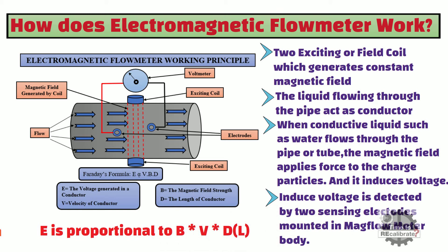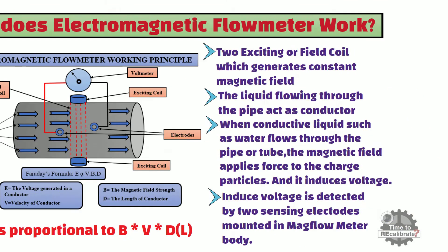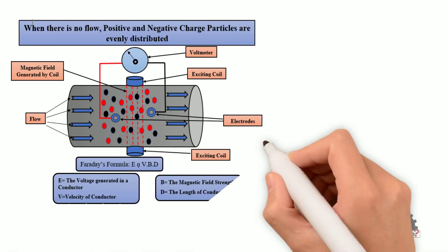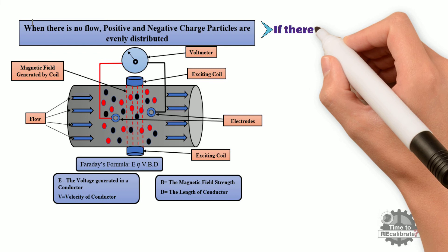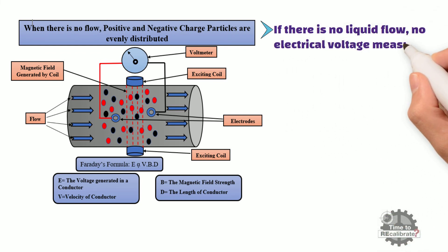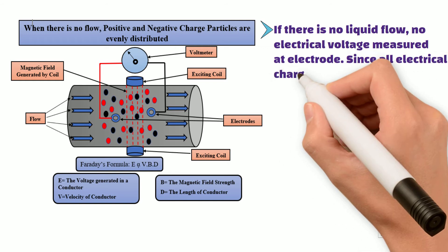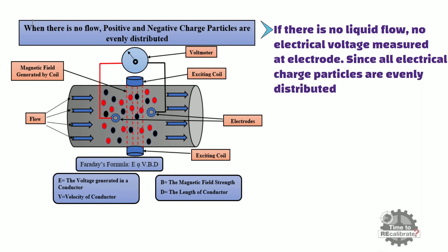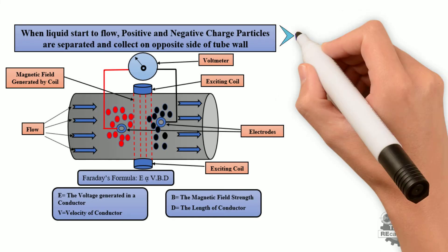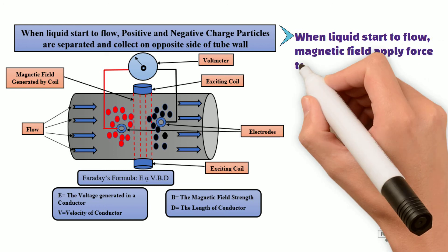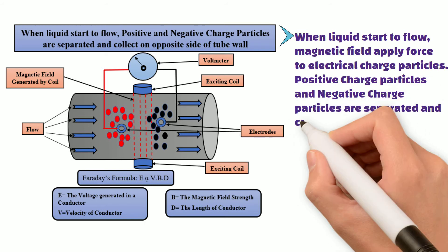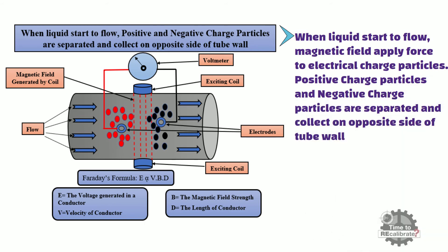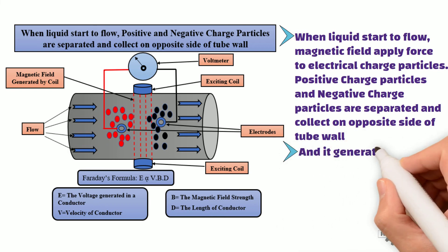In this equation, B is the magnetic field strength, V is the velocity of the conductor, and D is the length of the conductor. As you can see from the picture, if there is no liquid flow, no electrical voltage is measured at the electrodes, since all electrical charge particles are evenly distributed. When liquid starts to flow, the magnetic field applies force to the electrical charge particles — positive and negative charge particles are separated and collect on opposite sides of the tube wall — generating an electrical voltage.